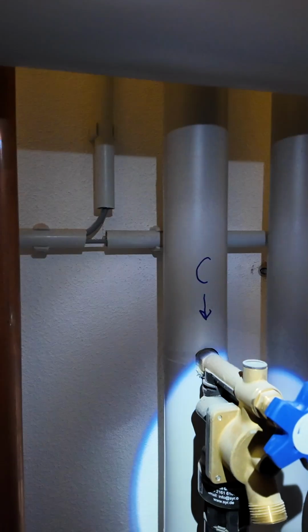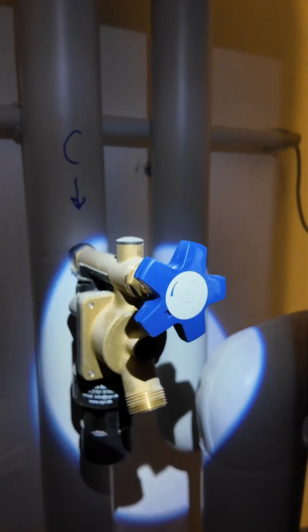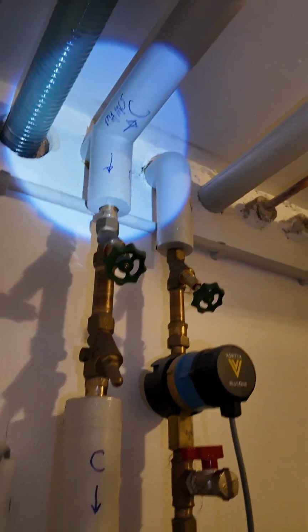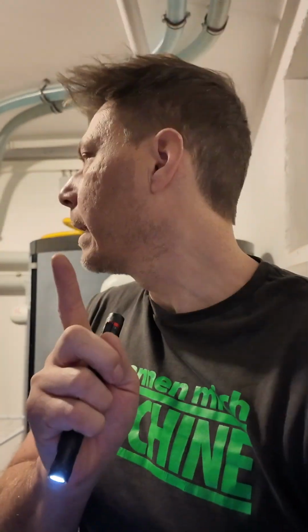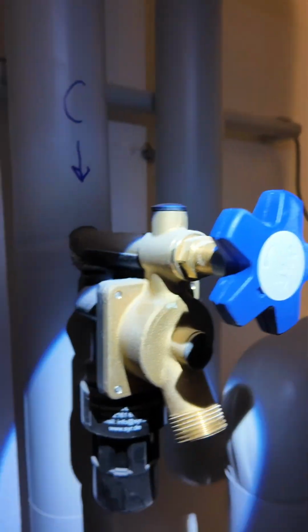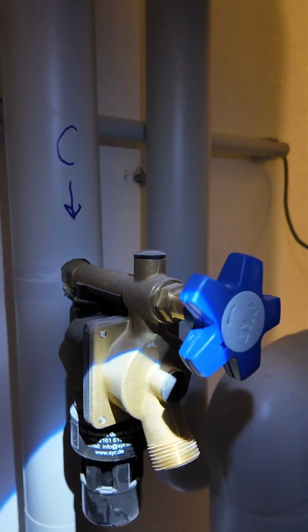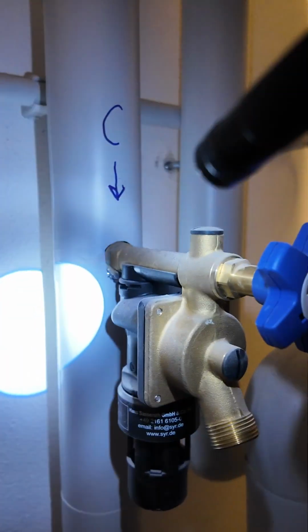So that has got a Rücksperrventil in there, which means, okay, this is actually the cold water coming in. So that comes from the mains all the way down to here. And this is what enters into the boiler at the bottom, but you don't wanna mix those two things. You don't wanna mix the Heizwasser, which is non-potable water, with your fresh water. So that's the reason that you gotta take it from this spigot here, because this spigot has a Rücksperrventil in there, meaning that the water can't go back up inside.